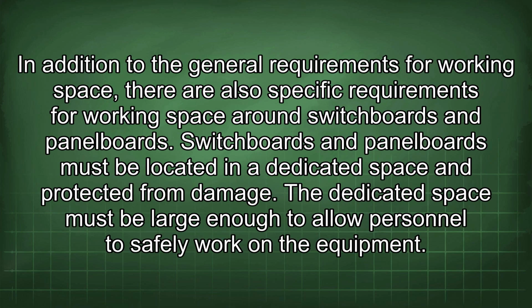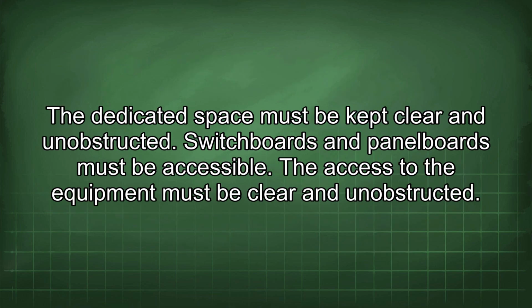In addition to the general requirements for working space, there are also specific requirements for working space around switchboards and panel boards. Switchboards and panel boards must be located in a dedicated space and protected from damage. The dedicated space must be large enough to allow personnel to safely work on the equipment. The dedicated space must be kept clear and unobstructed.